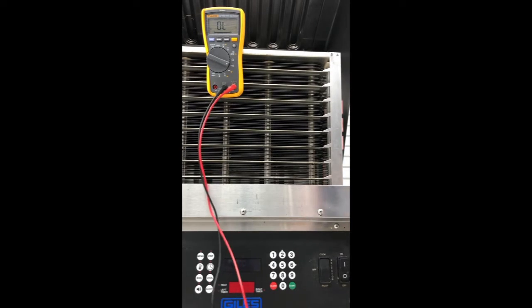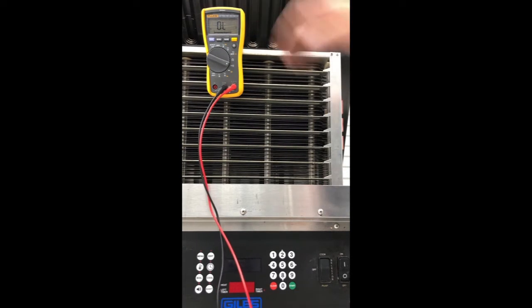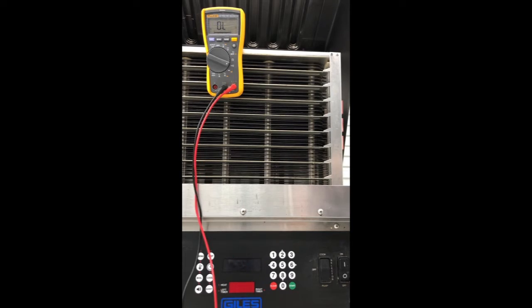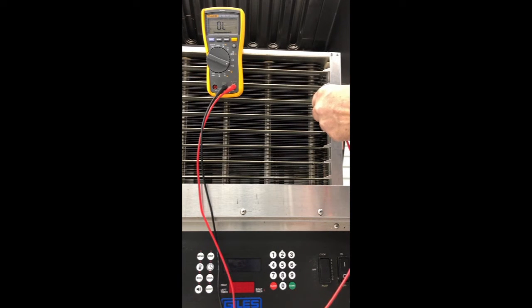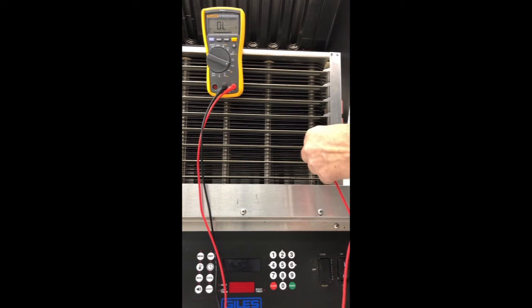One of the most common issues with the filter can be checked by using your basic ohm meter. You can put it on the sound side so that it'll give you a signal like that when you've got continuity. And to test it, you should have it against the frame. What you want to check is you have 3 contacts on the side. These 3 contacts, the 2 outside ones, serve the same purpose. They're actually applying power to the small fins. The one that we're worried about the most is the center. So if you touch the center, you should read it to each of these fine ionizer wires. You want to make sure you have continuity and that all of those wires are present and that they're tight.